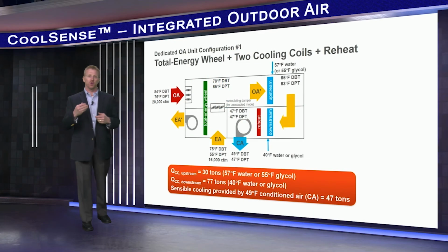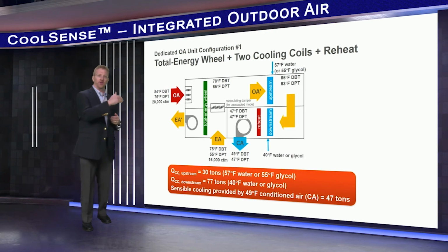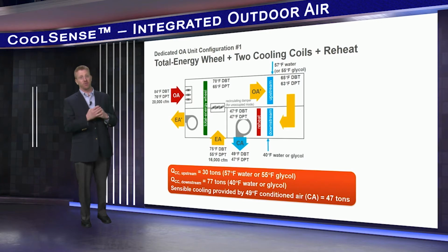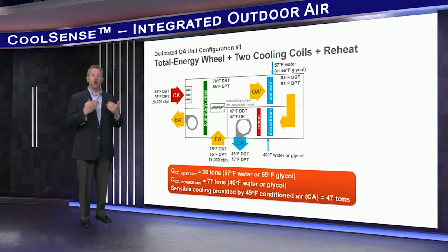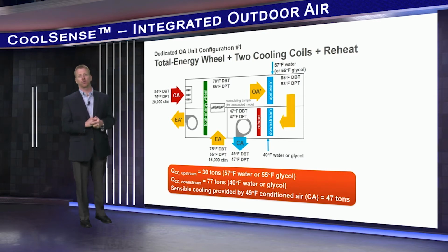That is, some of the load is shifted to the chiller operating with less lift, reducing the load on the tougher duty chiller that's making 40-degree water for dehumidification and ultimately lowering the chiller plant energy. This is not required, however, but it can be valuable if you're trying to maximize overall efficiency or minimize the size of the cold water chiller.